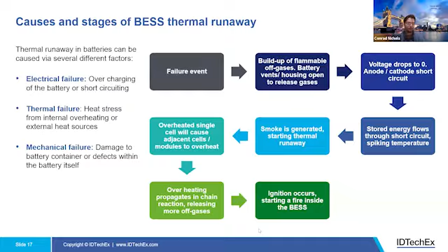Once a failure triggers thermal runaway, it's the gas evolution during the event that causes fires and explosions. Off-gases from the battery cell can include carbon dioxide, carbon monoxide, and fluorine-based gases, which can react to form explosive and flammable hydrogen gas. As these gases evolve, pressure builds up within the cell and system, and once a critical point is reached, the battery will rupture with the gases potentially igniting—so you can have a fire and explosion happening simultaneously, which can be catastrophic.